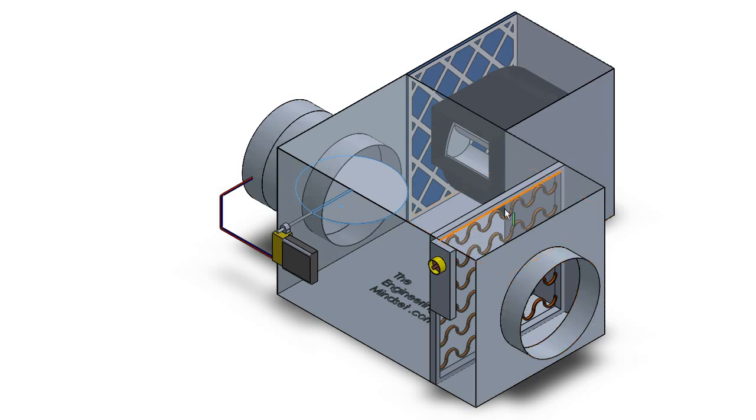And that will and can pass through the heater battery if required and off into the zones. And that's useful because the fan will keep a constant volume coming through the box. So if you imagine as that damper closes, then less air volume will be coming through. So the fan will ensure that a consistent volume is coming through that box. So you get the air turnover in the room.